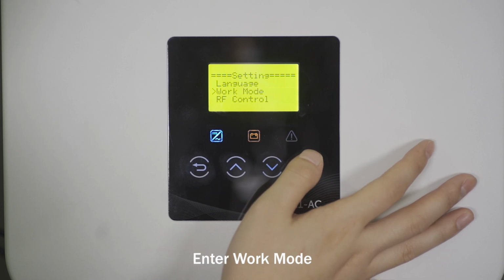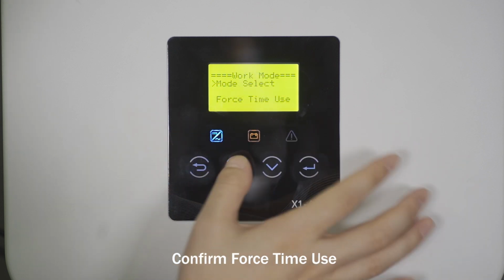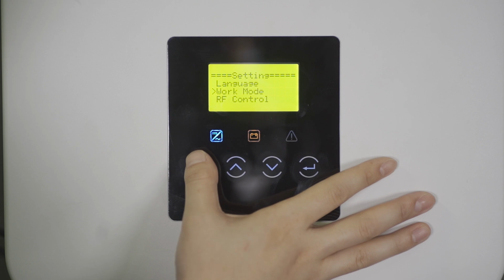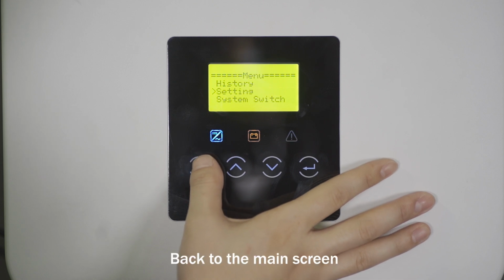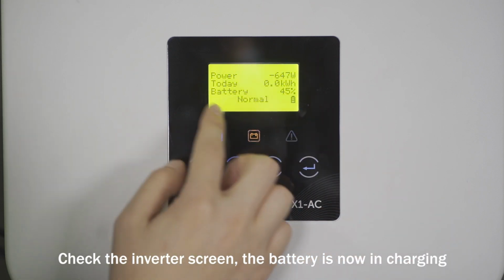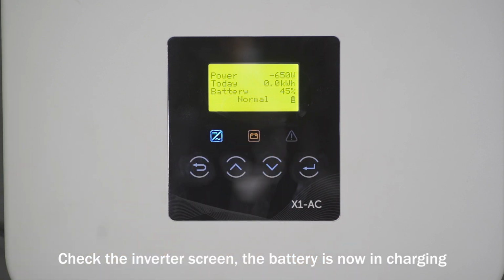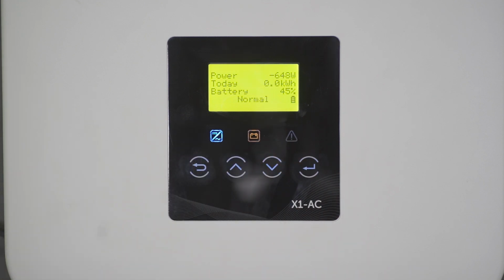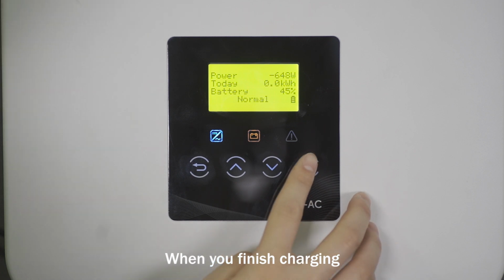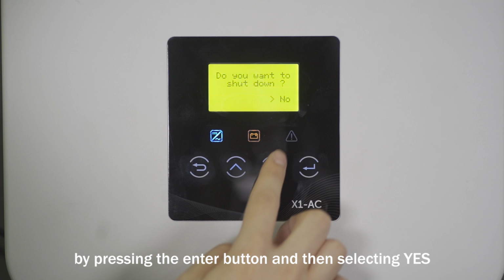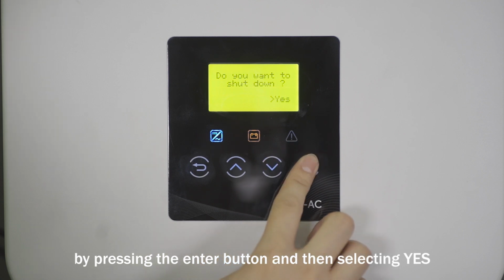Back to setting. Enter work mode. Confirm force time use. Back to the main screen. Check the inverter screen. The battery is now in charging. When you finish charging, you can shut down the inverter by pressing the Enter button and then selecting Yes.